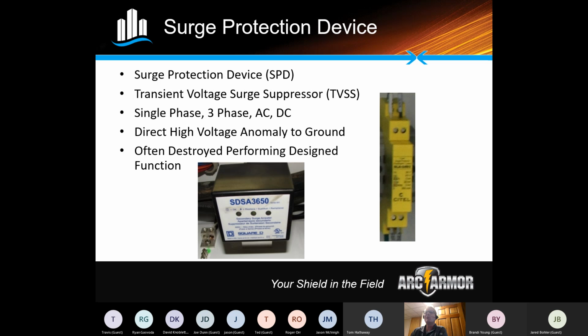So normally where you see these installed, right? A surge suppressor, or surge protection device, you're going to see installed on the main incoming line into a panel or prior to the panel, and they'll be three phase or single phase. Many other times you're going to see surge installed in a panel is on any circuits that are leaving a building or leaving that control panel.